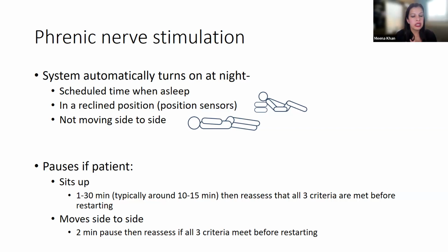The range we can program for that is 1 to 30 minutes, but typically we do around 10 to 15 minutes. After that time has passed, the device assesses if all three criteria are met. So the time is after the time they should fall asleep, they're in the reclined position, and they're not moving. If all those are met, it will restart therapy. If the patient moves side to side, we can program a pause time for that. Typically we do around 2 minutes. Again, after that time has passed, it'll reassess all three criteria. And if all three are met, it will restart therapy.